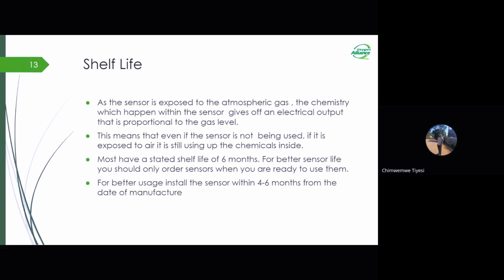Most electrochemical oxygen sensors have a stated shelf life of 6 months. You may ask why 6 months. Of course, I will talk about it in the following slide, about the lifespan of the electrochemical sensor, which is about 2 years. If you're buying an electrochemical sensor which has already been on the shelf in a shop or store for more than 6 months, that means you are drastically reducing the lifespan, or the time you can reliably use this electrochemical oxygen sensor. So for better sensor life, you should only order sensors when you are ready to use them. Again, for better usage, install the sensor within 4 to 6 months from the date of manufacturing.